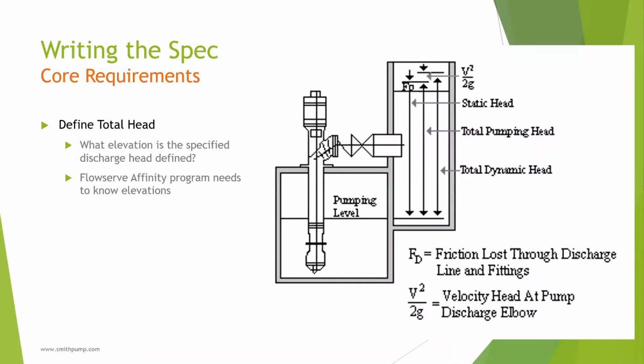Without getting into a pump hydraulic class, we need to know the elevation at which the specified head was calculated. There are typically 2 points, the low water elevation or the discharge center line. It matters because the pump has to produce more head than requested if the TDH is based from the discharge center line. You can see the extra static head elevation the pump must produce from the red arrow. And I brought this up because Flowserve has a sophisticated pump selection software called Affinity. It needs the correct elevation to make accurate selection. So let me show you a quick behind the scenes look of how the Flowserve software does all these heavy calculations. I don't understand their methods, but I do know that elevations are important for a good pump selection.